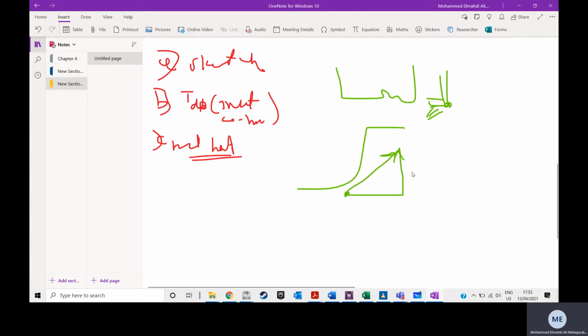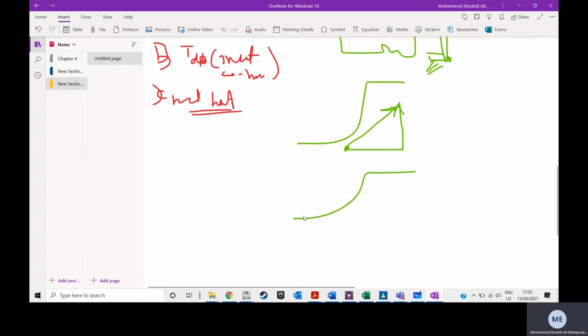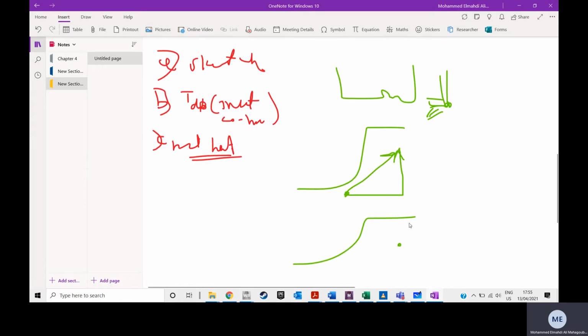But in cooling and dehumidification, the same thing cannot happen. In simple cooling, I don't have a device that does dehumidifying. When I want to dehumidify, my cooling coil surface temperature should be lower than the dew point temperature in order for condensation to happen. So what happens is that I slide across this line, then I end up where I want. And this will be my process line.